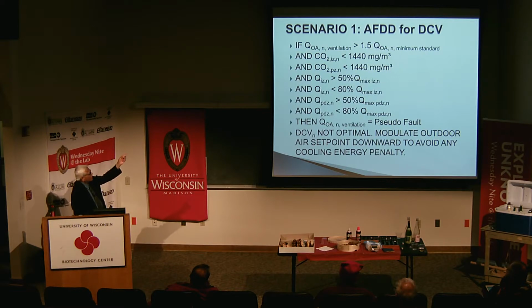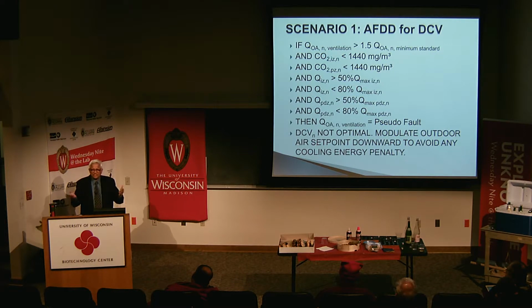Now, I have used rule-based algorithms for all these AFDD. There are other types of approaches taken, like statistical approach, virtual sensors, model-based, predictive control and all. The approach I took was rule-based. The reason I took rule-based was, if you look at HVAC, there are only finite decision-making you have to do. When I say finite, maybe 50 or 60, you can do it. And rule-based approach is somewhat intuitive. Just like when you have a problem with your HVAC, what do you do? You say, maybe this happened. If this happened, that should have happened. That's it. That's a rule-based approach.